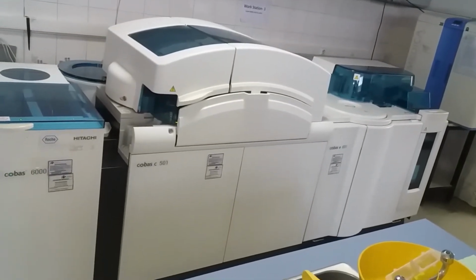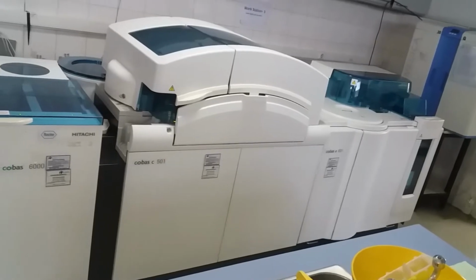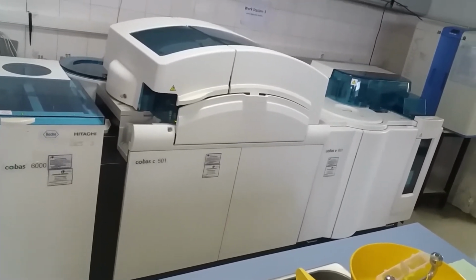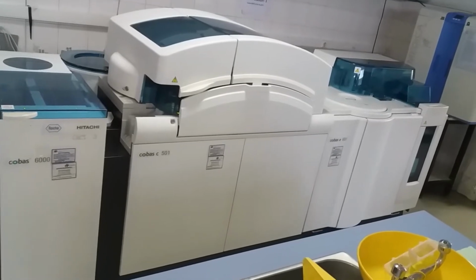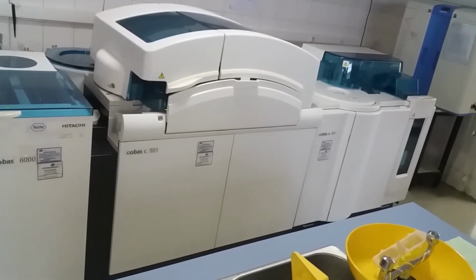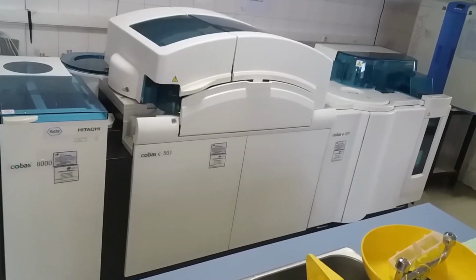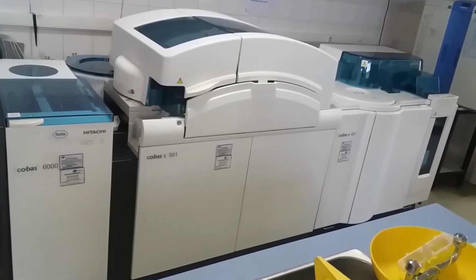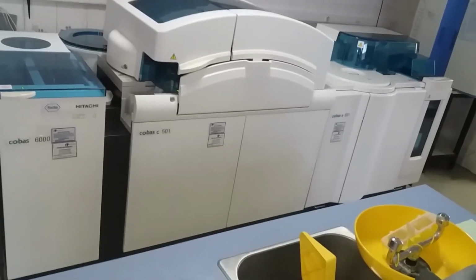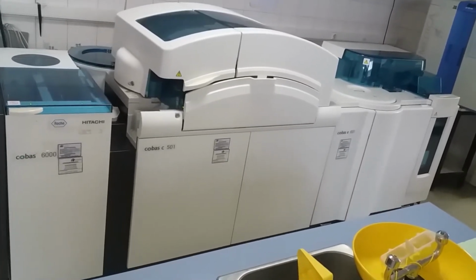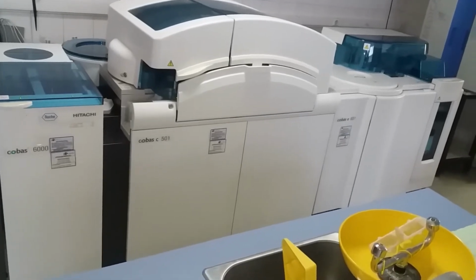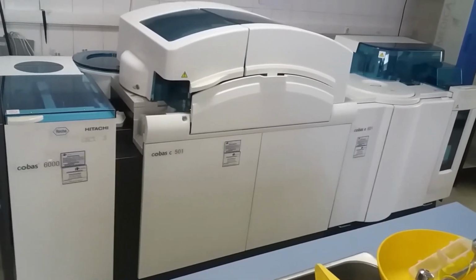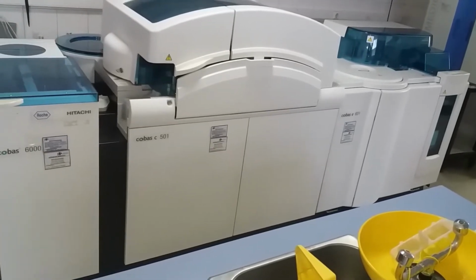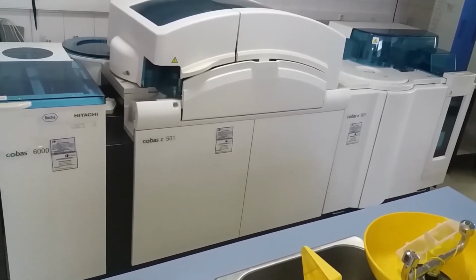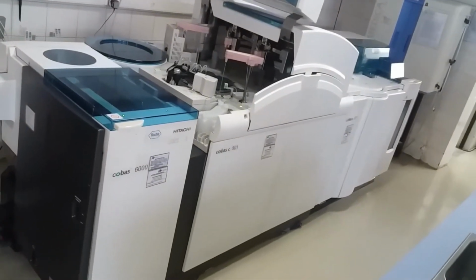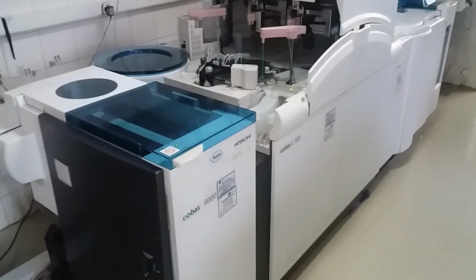The other major equipment found at the National Clinical Chemistry Reference Laboratory is the Cobas 6000. When we see the product specification of this Cobas 6000, its testing capability is clinical chemistry, ISE (ion selective electrode), hemoglobin A1C whole blood measurement, and immunoassay. Throughput is up to 1000 tests per hour combined with photometric and ISE ion selective tests.